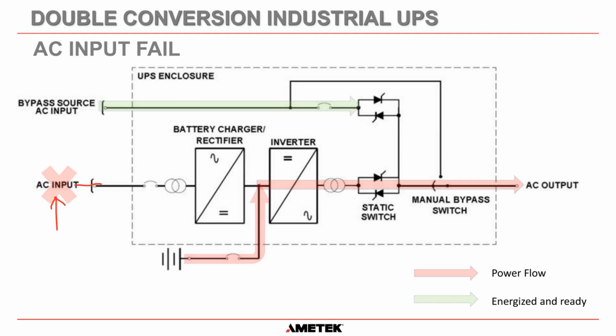So the AC input power to our rectifier battery charger has been lost. So what happens is, now a lot of people say that then it switches to battery. There is no switching here that happens. It's just as if, I'm sure everybody has a laptop these days. If you pull the power out of your laptop, it just continues running as normal because the DC bus in that laptop is in parallel with the battery. And that's exactly what happens inside our UPS systems. As soon as the charger loses power, the batteries just continue taking the load without any issues whatsoever. There's no switching. They just take over supplying current to the inverter.